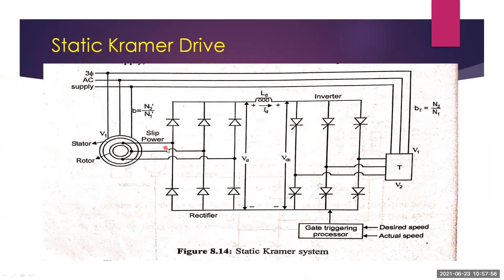In the static Kramer drive, the slip power is not wasted in the rotor circuit resistance — it is fed back to the supply. In the conventional rotor resistance control method, the slip power is wasted, but here the slip power is fed back to the supply through a step-up transformer. This is the main advantage of the static Kramer drive.